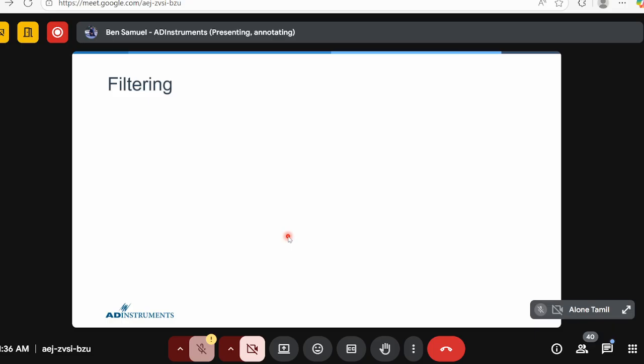Next is filtering. Why do we need filtering? In a signal, there will be something called noise, which is nothing but an unwanted signal. So we have to filter those. For that, in our hardware, the PowerLab, we have something called hardware filters, and in the software, we have something called software filters. With hardware filters, we have to be very sure of what we are doing, because once the signal is acquired, you cannot revoke those settings. Whatever signal is coming in, you have to be very sure.